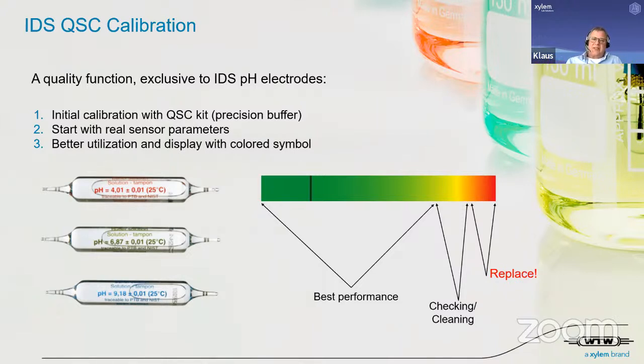We start with the real values of the sensor, which is set to 100%, and then we have a fine grading between the maximum (100%) and the point where people should consider cleaning or maintaining the sensor, and finally replacing it. The best performance is in the green range, turning to yellow, then orange, at which point people should think about maintaining the sensor. At the red end, it's time to replace it.